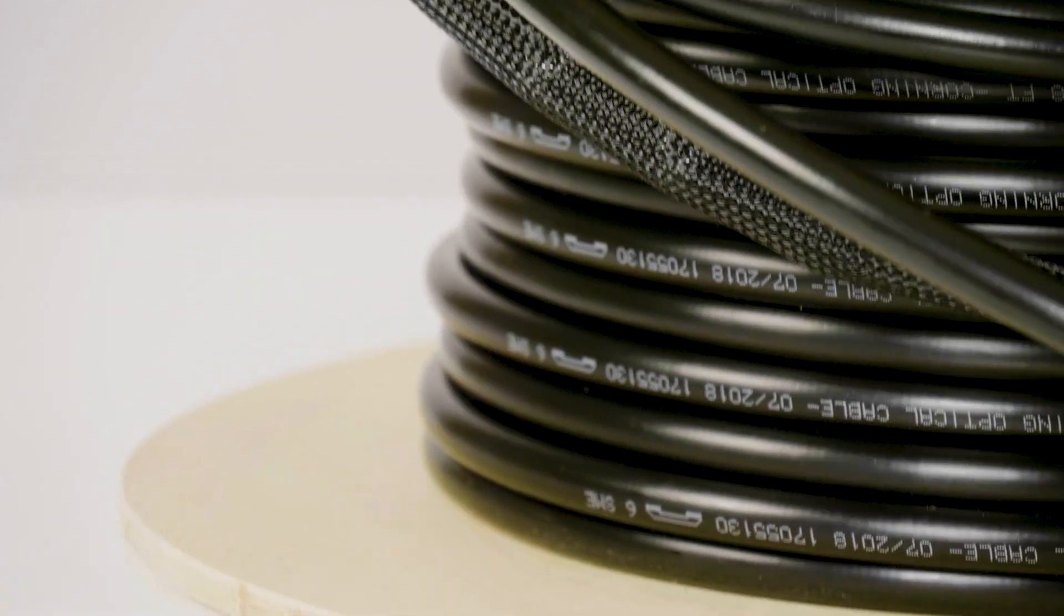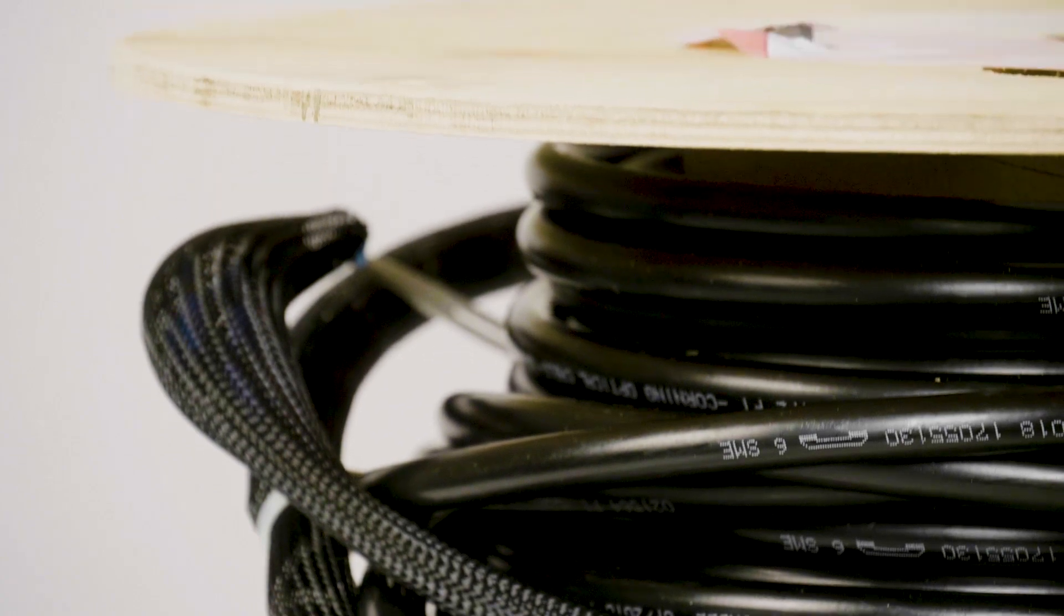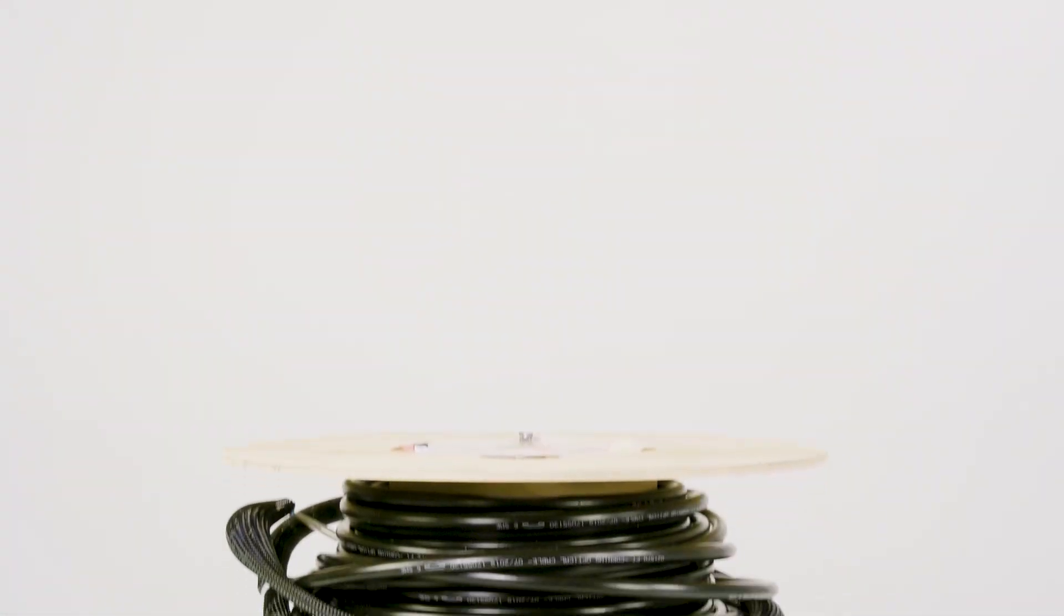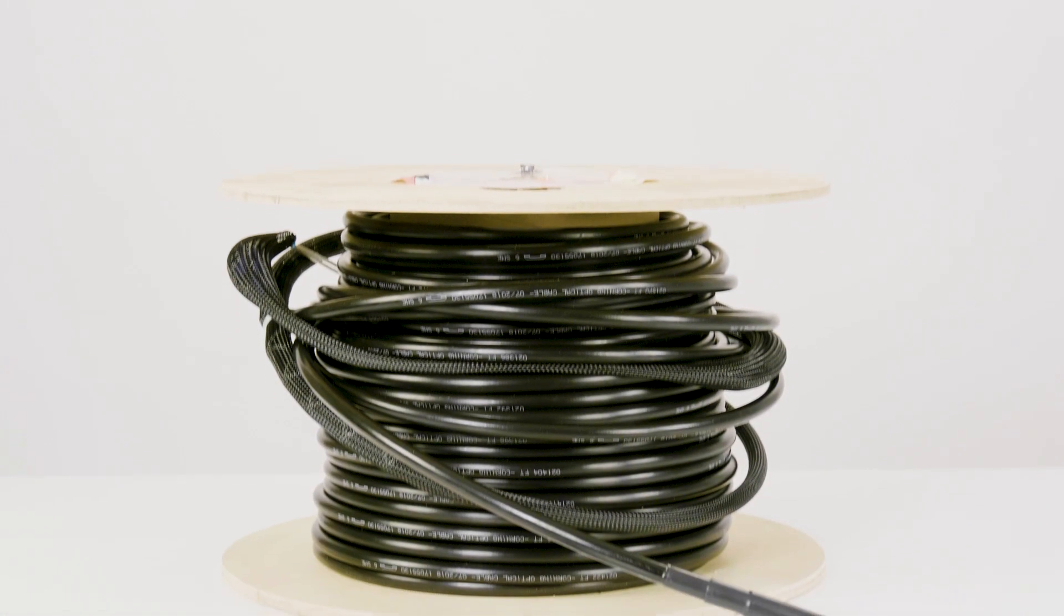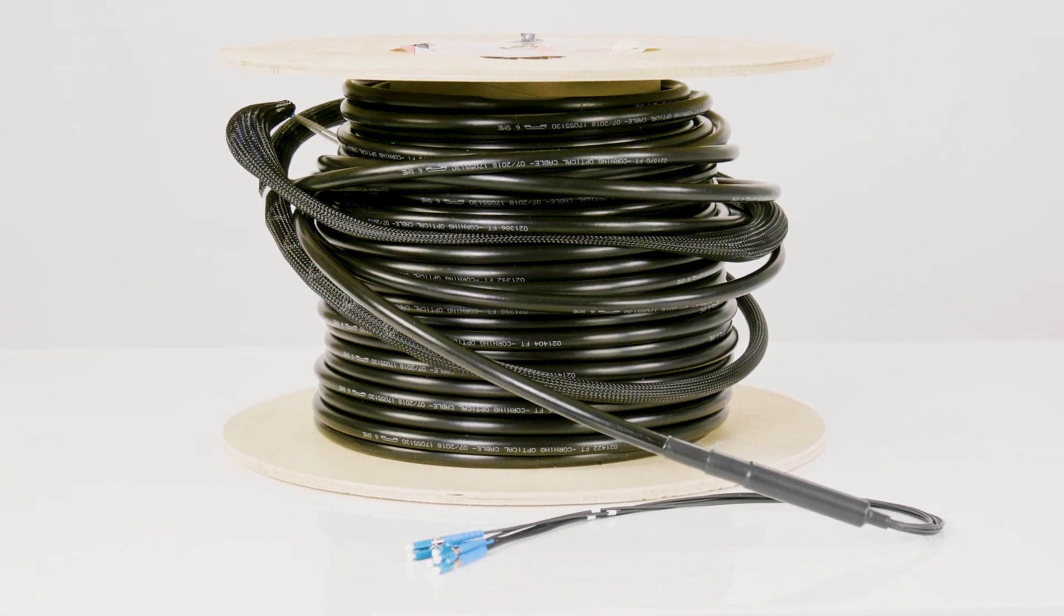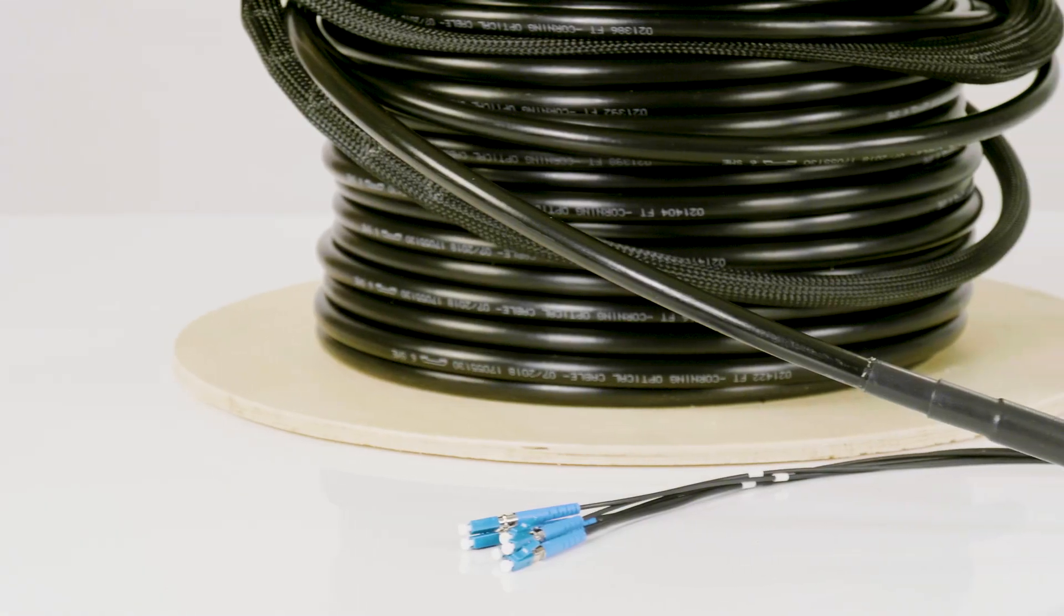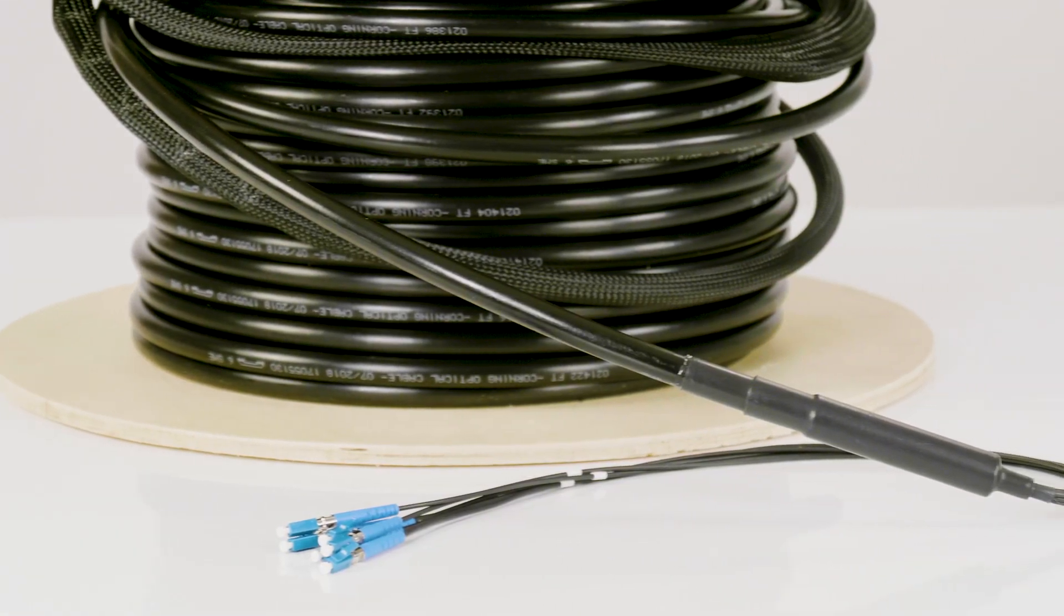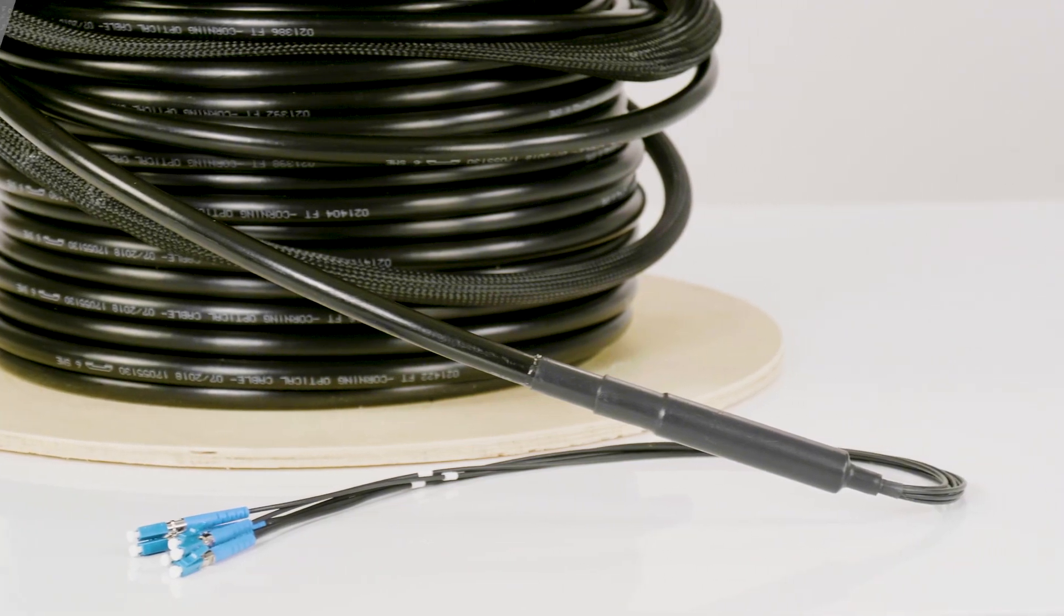Another tip and a very important thing to keep in mind is to properly ground these cables. They should be grounded at all termination points, splices, and building entrances. The cable's steel armor should be connected to a ground wire using a compression type clamp. The cable ground wire is then bolted to a nearby ground terminal strip.